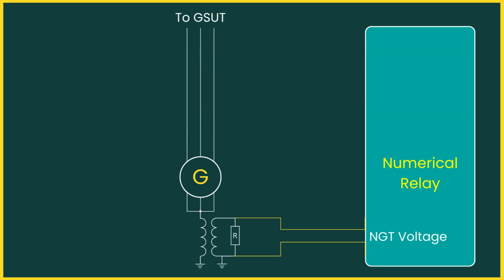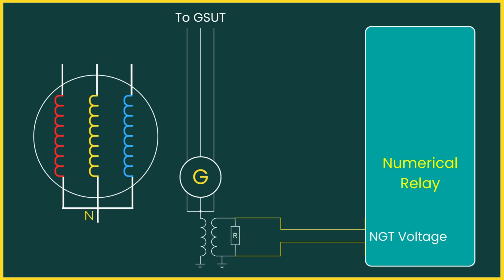The NGT method is the most direct way to measure neutral displacement. In this approach, the neutral voltage displacement is detected across the NGT. This measured voltage reflects the neutral to ground displacement, and its magnitude increases as the fault occurs farther from the neutral point. For example, in a 22 kV generator, the phase-to-neutral voltage is 12.7 kV. If the NGT ratio is 22 kV to 220 volts, a terminal fault produces a secondary voltage of 127 volts.